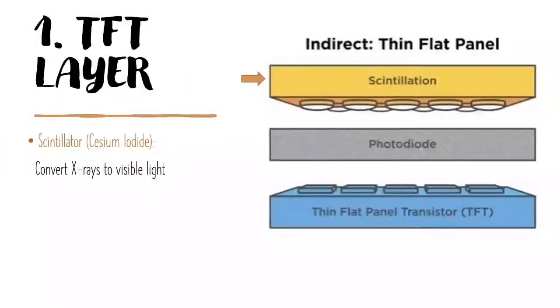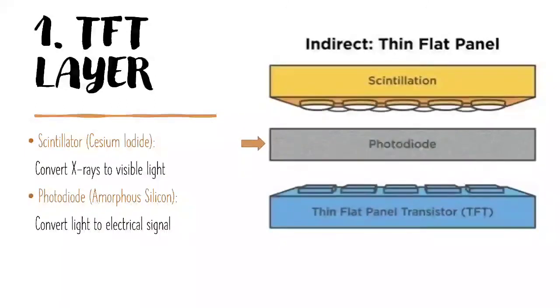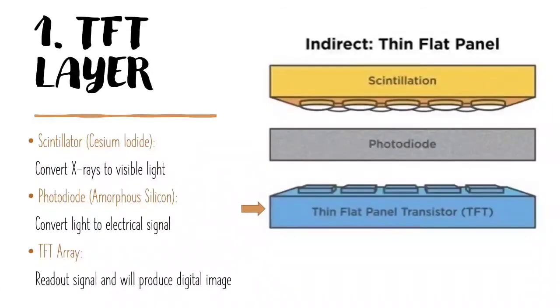Next is the TFT layer. The first layer is the scintillator, made of cesium iodide, and its function is to convert x-ray to visible light. The next layer is the photodiode, which consists of amorphous silicon and converts light to electrical signal. The last one is the thin film transistor, or TFT, whose function is to read out the signal and produce a digital image.